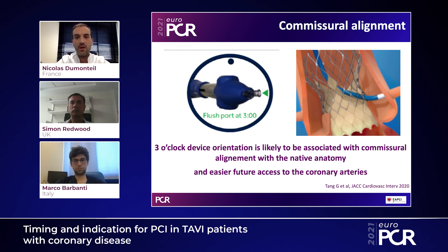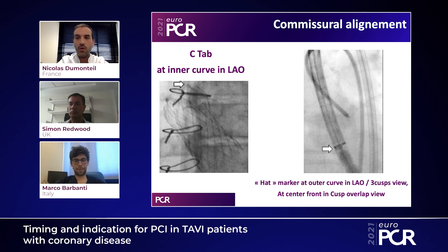For the Evolut frame, good commissural alignment can be anticipated at the time of introduction by positioning the delivery catheter with the flush port at 3 o'clock. This can also be validated once inside the aortic root. There is a Hat marker at the distal tip of the Evolut frame: in LAO or Coplanar view, if the Hat marker is at the outer curve, you'll likely have good commissural alignment; in cusp-overlap view it should be in the center front. Once the valve is released, a C-tab at the outflow portion of the frame located at the inner curve in LAO confirms proper commissural alignment.